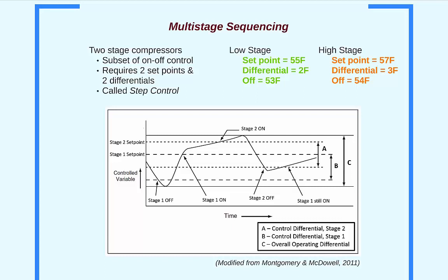When the supply air temperature increases above 55 degrees, the first stage turns on. As the evaporator removes heat, the temperature decreases. When discharge temperature reaches 53 degrees, the low stage turns off. The discharge air temperature begins to climb. Once it hits 55, the low stage will turn on. If there isn't enough capacity, the discharge air temperature will continue to rise. When the discharge air temperature hits 57 degrees, the second stage will turn on to provide additional cooling. Assuming the unit was sized correctly, the discharge air temperature will begin to fall back to set point. When the discharge air temperature reaches 54 degrees, the high stage turns off.